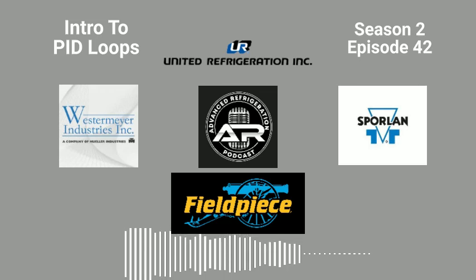So one prime example of this, we have a Cascade rack in one of our stores in Texas, and I adjusted the crap out of the PID loop for the electronic expansion valves, and when it got cold, everything fell on its face. I had to be there for about 4 hours to get a pseudo good adjustment on the superheat controller to get it to react a lot faster than what it was. And I had to do it when it was cold, because it worked fine when it was warm outside, but as soon as it got cold out, my programming went out the window. It was garbage. So when you have those drastic changes in temperatures, it is going to affect the way the thing reacts.